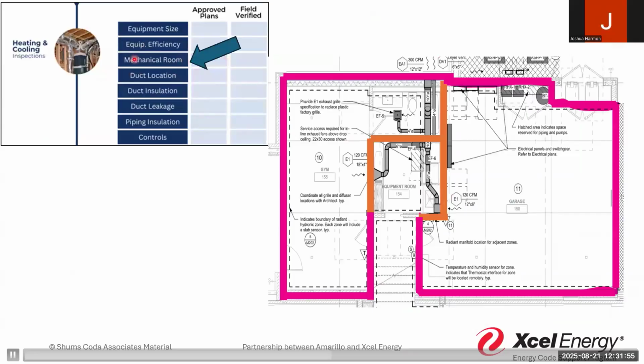What I'm talking about when I say mechanical room is making sure we understand the relationship between the mechanical room or wherever the appliance is and the thermal envelope. The code requires that thermal envelope be continuous around that equipment room when it gets its combustion air from an uncontrolled venting system. So if it's getting uncontrolled, untempered air directly from outside into that combustion area, we need to make sure we're not allowing that air to migrate into the surrounding conditioned space and cause heat loss.